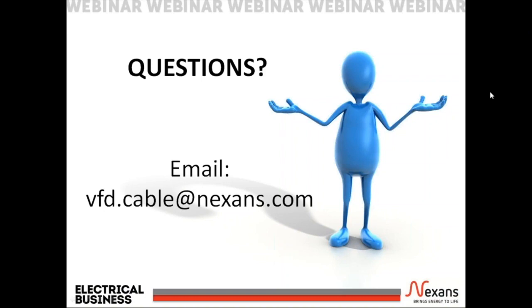So currently, within the Canadian Electrical Code for Canada and the National Electrical Code for the US, I'm not aware of any requirements for VFD cables for VFD systems. I can't really say why that is for sure. I believe that there should be some requirements in the code, from an electrical shock point of view and from a hazardous location point of view. So there is good safety justification.